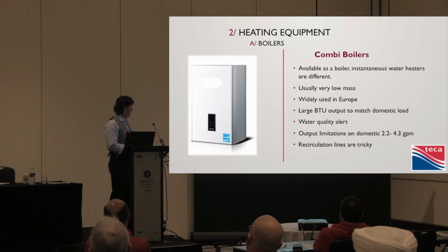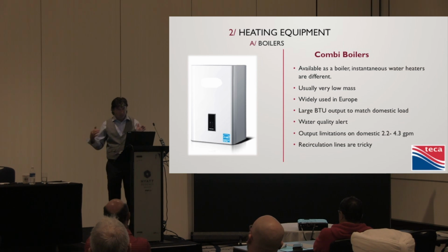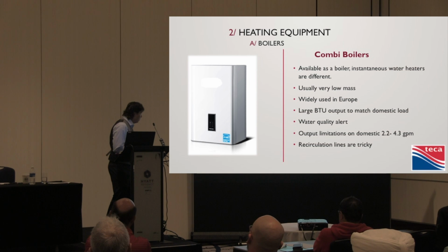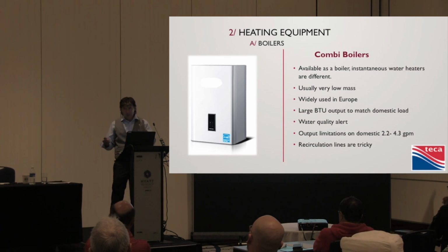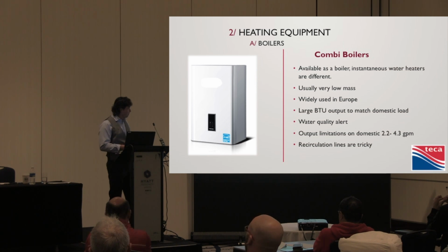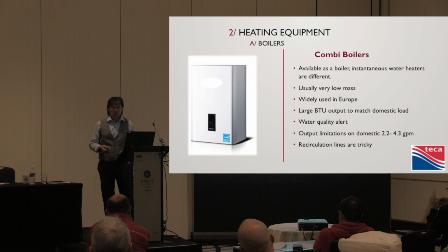Yeah, so that's the other thing, is the output limitations. Because we're heating water instantaneously, we already know we're taking like 200,000 BTUs to heat this water instantaneously. And when we do that, what do we got? 2.2 to 4.3 in the literature I looked at, all the different varieties. So the biggest one, you're up around 4.3 gallons per minute. Okay, well, how much water is that? How much water is 2.2?